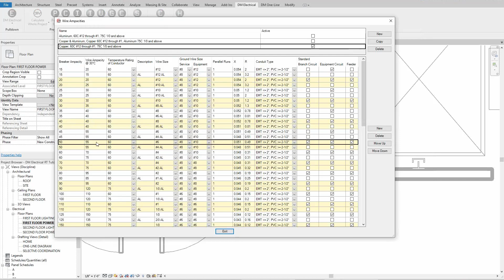However, we are also now recording the wire ampacity, which in this case is 40, and then the temperature rating of the conductor for this whole configuration, 60 degrees. If we come down to the 50 amp line, you can see that the wire ampacity is 55. So the wire actually is rated for something higher than the breaker. We can use this when we then derate the wire for multiple runs of wire in a conduit and for the ambient temperature.